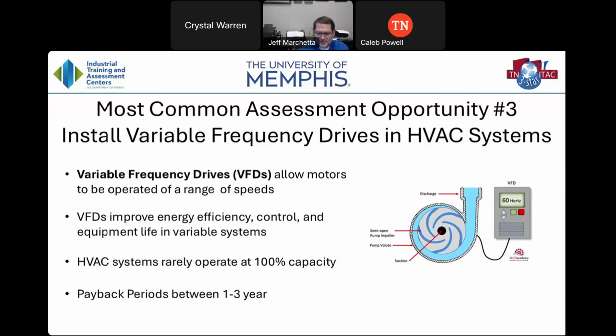In fact, you're actually losing energy because the drive itself has roughly a 1 to 2% energy loss associated with the inverter. So what you want to see is that number at 60 hertz vary according to the system it's attached to and whatever is driving the speed control, whether it's temperature or pressure.